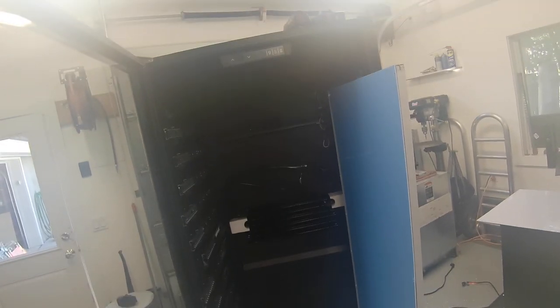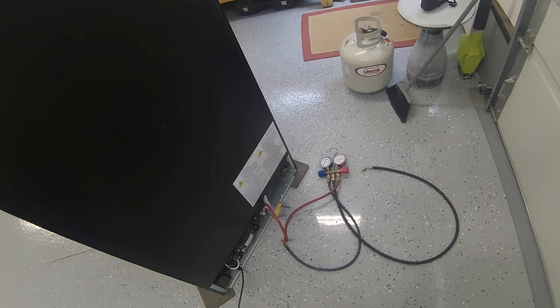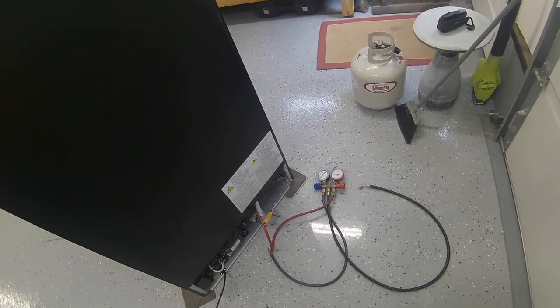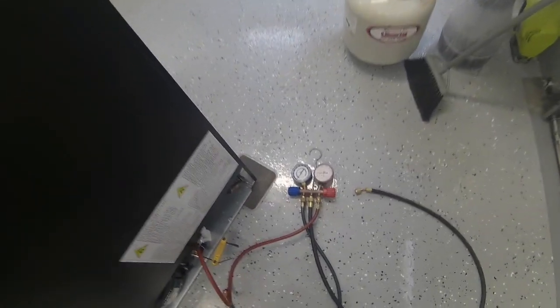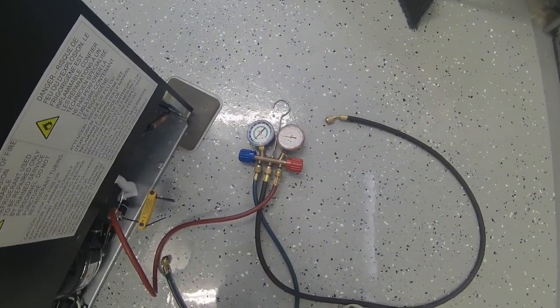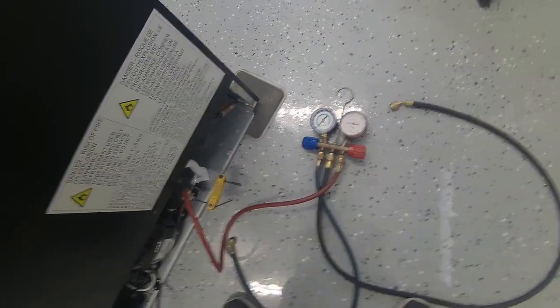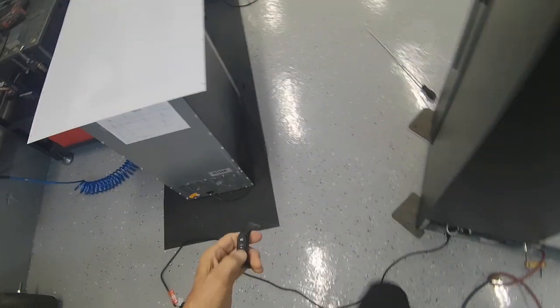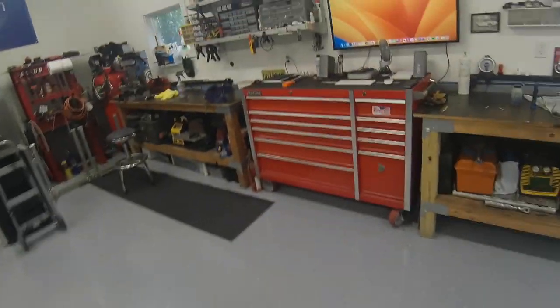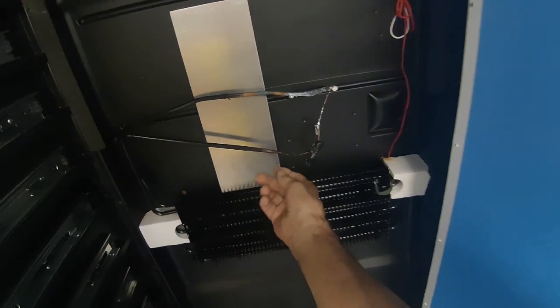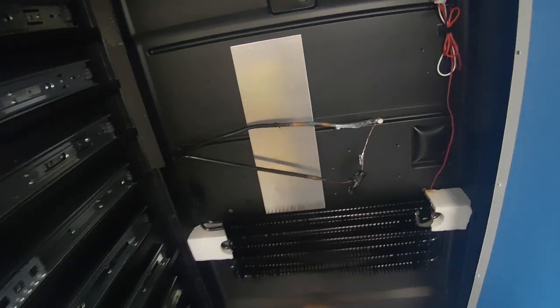See you later. Okay, we let this machine sit there overnight at 100 pounds pressure on the high side, and it's still 100 pounds, so I don't see how it would have a leak. Okay, so I've checked all the joints for leaks.